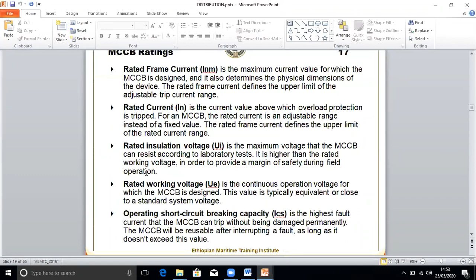That means from the main switchboard, let's say for the steering gear, you will have a feeder circuit for 440 volt. There you will find an MCCB like this. From this MCCB, the power supply will go to the steering gear starter. Okay, so this is the feeder circuit MCCB. Generally, when it is tripped, it will be in the middle. It will not come down fully if it is tripped. So you need to reset it: push it down and pull it up. Then it will get reset. So MCCB is generally used as the feeder circuit breaker.